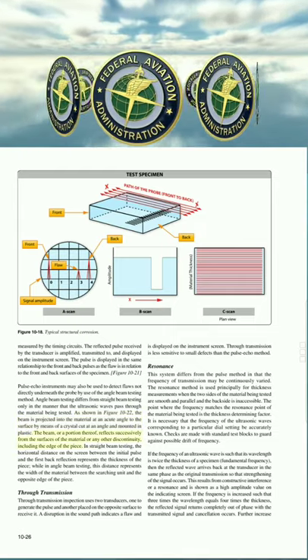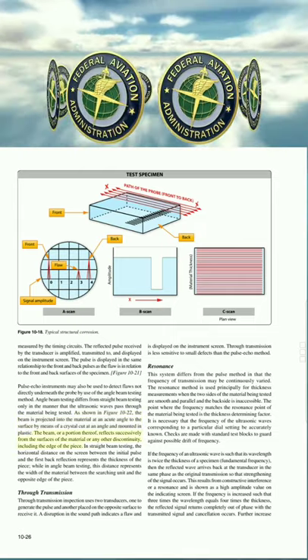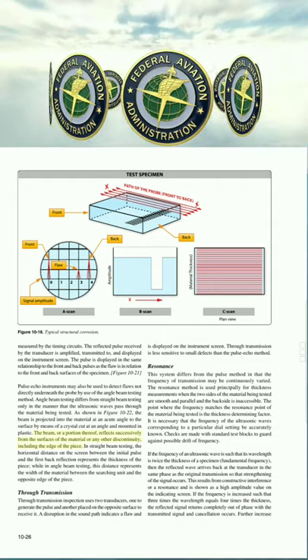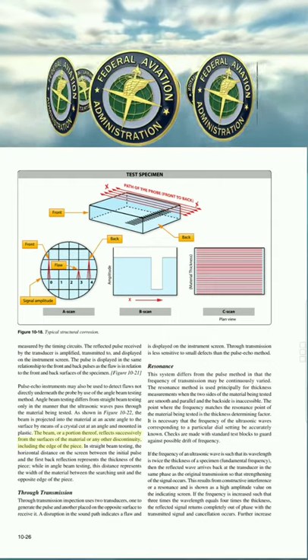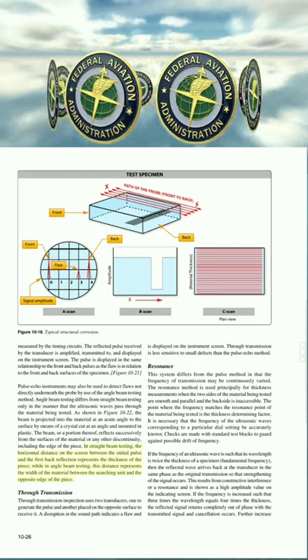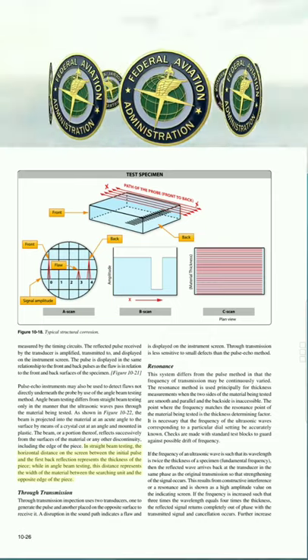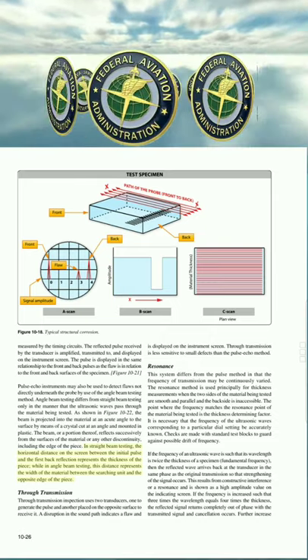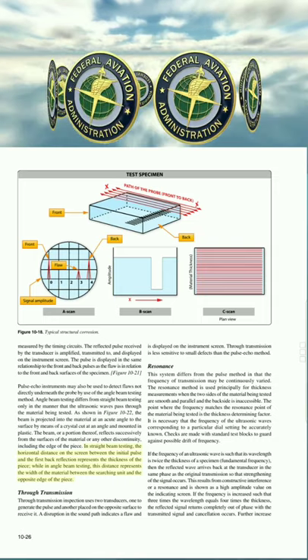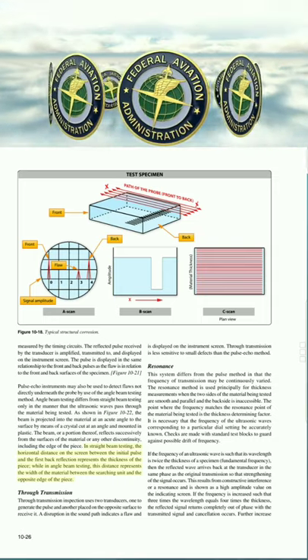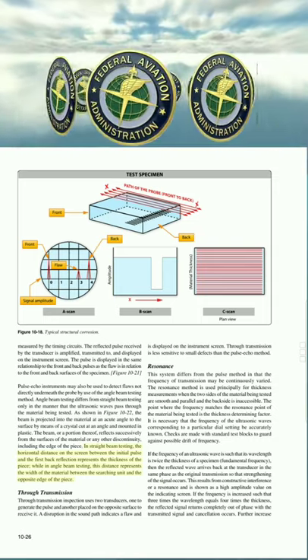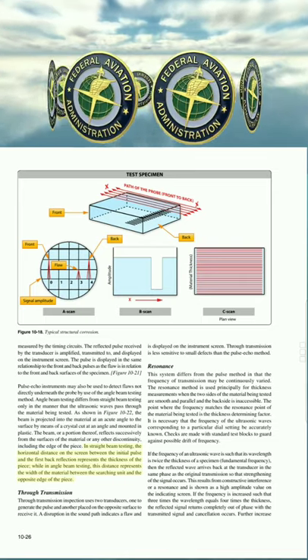The beam, or a portion thereof, reflects successively from the surfaces of the material, or any other discontinuity, including the edge of the piece. In straight beam testing, the horizontal distance on the screen between the initial pulse and the first back reflection represents the thickness of the piece. While in angle beam testing, this distance represents the width of the material between the searching unit and the opposite edge of the piece.